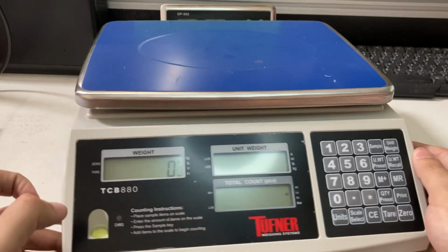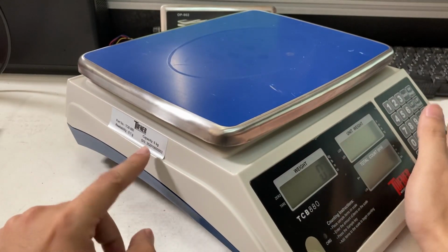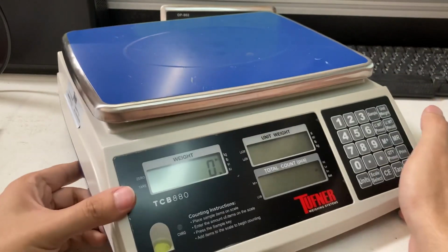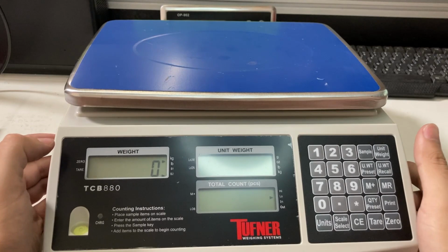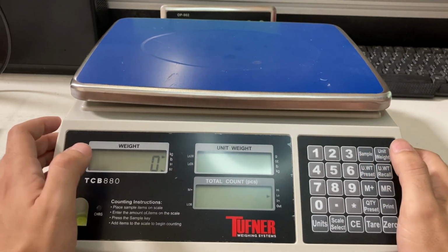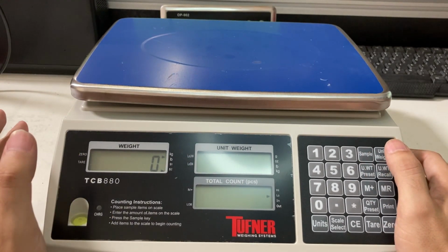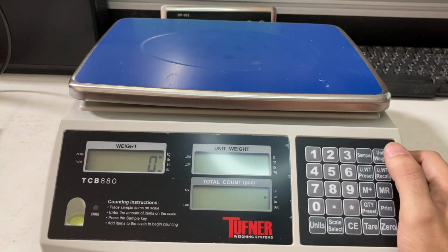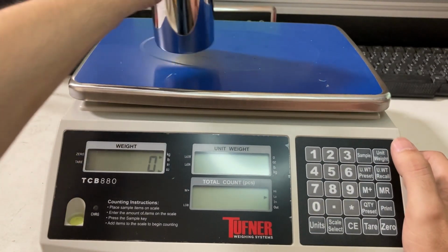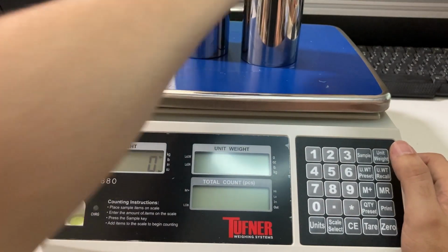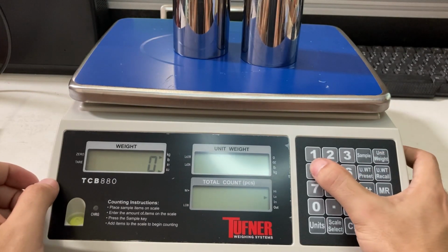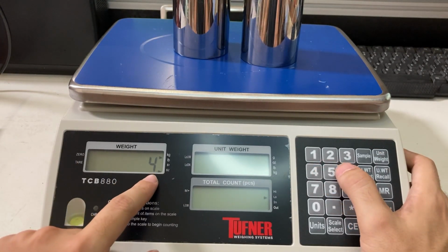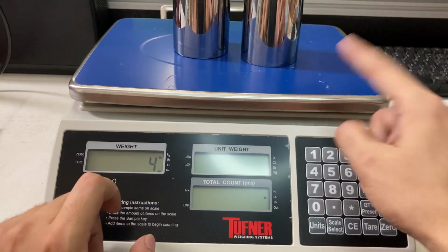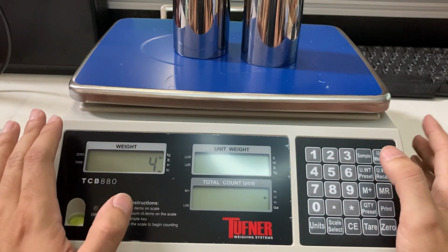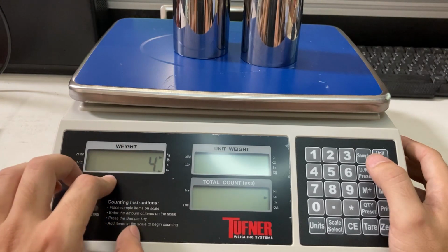My specific model, if you check the side, has a capacity of 6 kg. That's the maximum, so for calibration of the top pan, they recommend 2/3 of it, which in my case is 4 kg. So I'm going to grab a 2 kg weight, and here's another 2, so that's 4. Now you type 4, or whatever your 2/3 max capacity is, and put that on the scale. It has to be 2/3, that's what the manual recommends. I haven't tried it with other weights, but that's what I used.